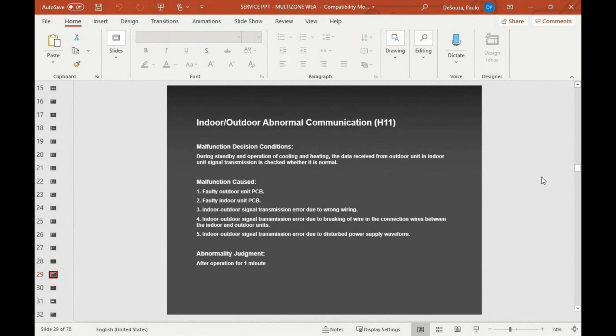Now, we are coming to the section of error codes. Okay, guys? We are coming to the section where we are talking about troubleshooting. And guys, just remember, I'm reminding you once again that this is a multi-zone slide, but the troubleshooting error codes also apply to single zones. Okay? Same error code in multi, same error code in singles, except for 2 error codes, F17 and H39, which is standby freezing or cross wiring on a multi-zone. Okay, guys?